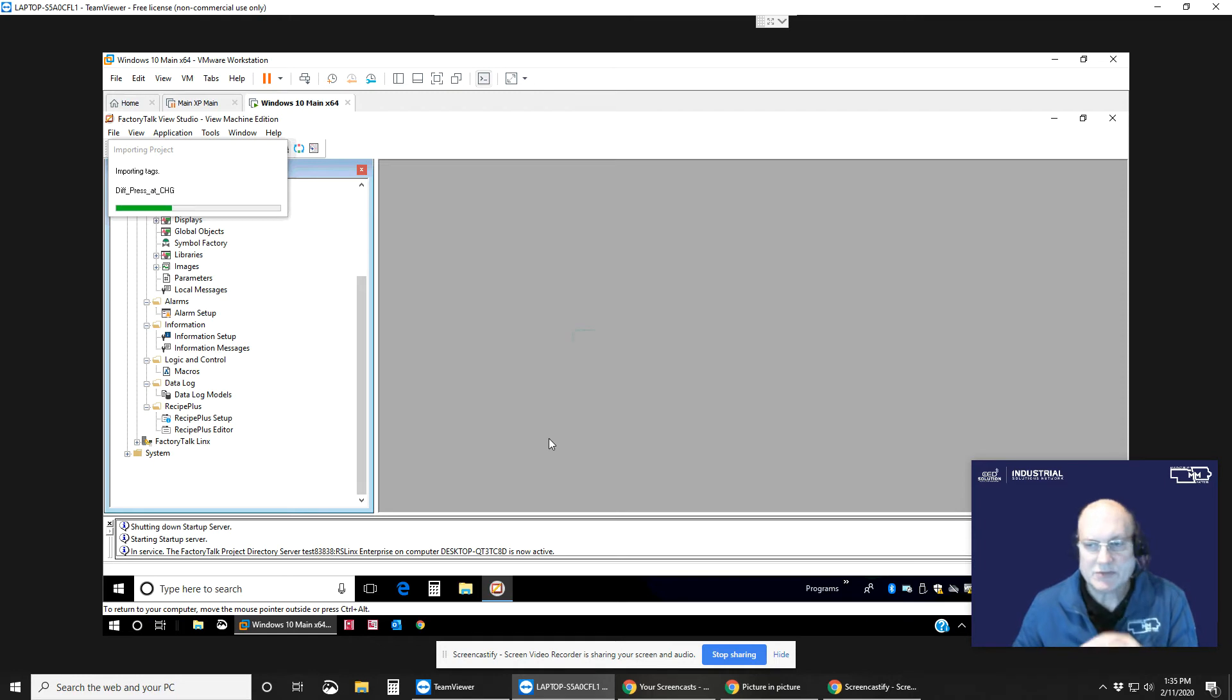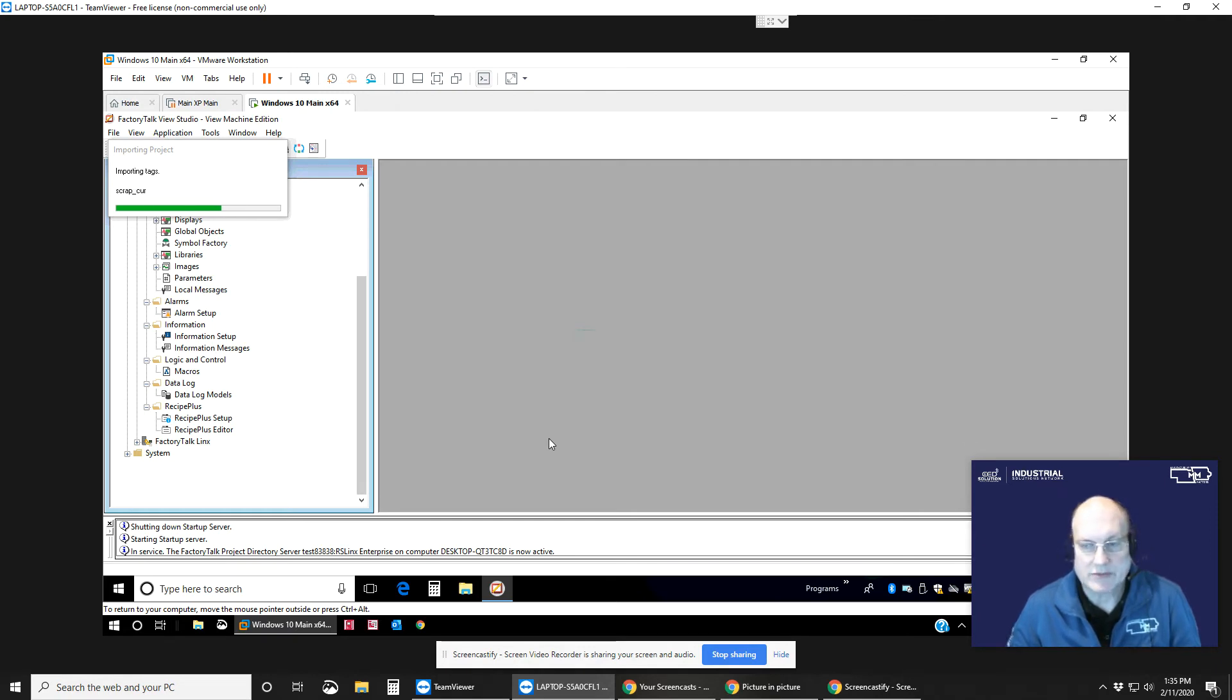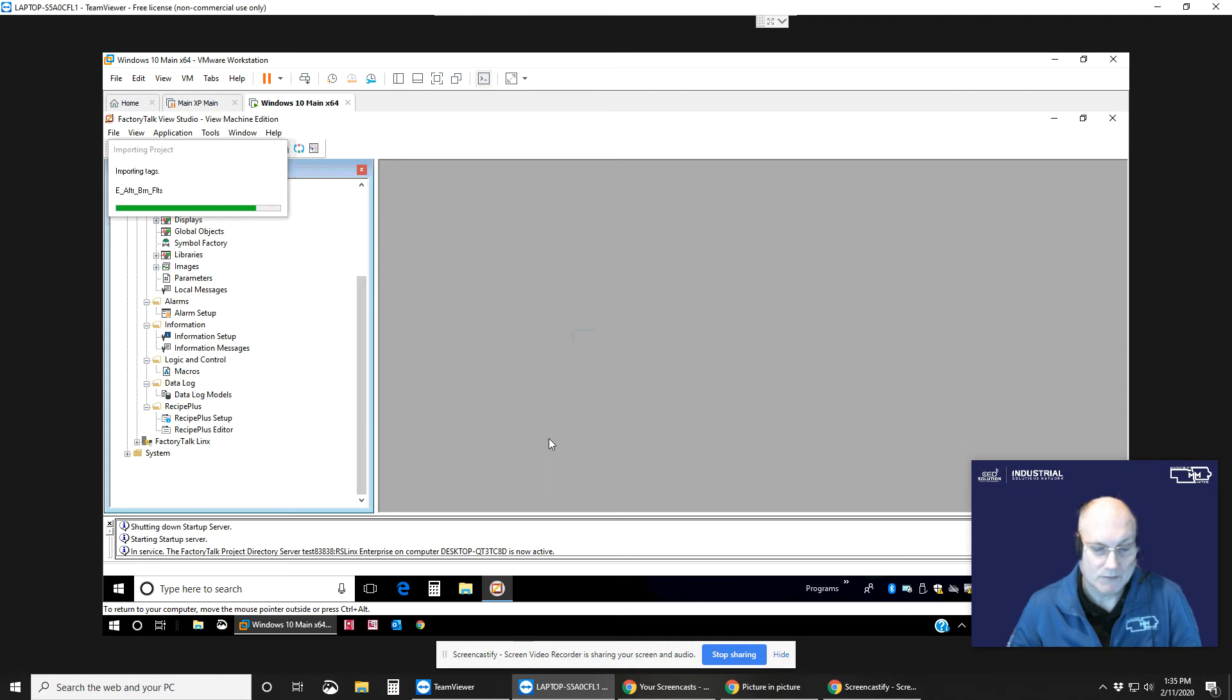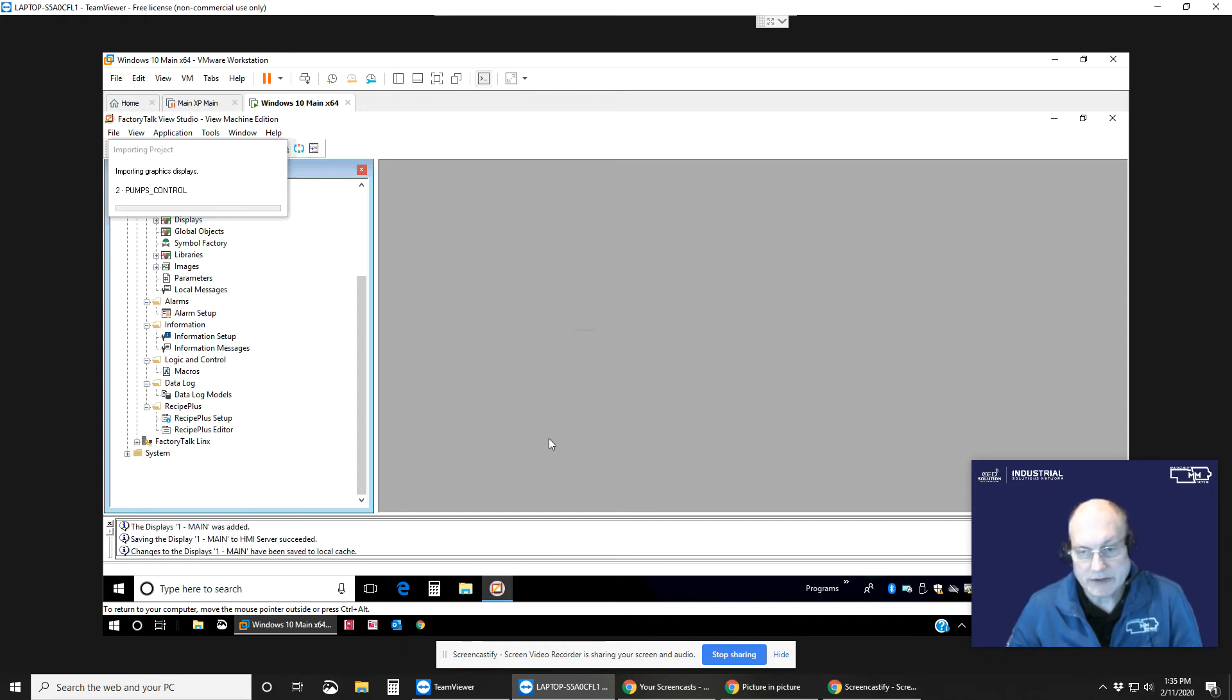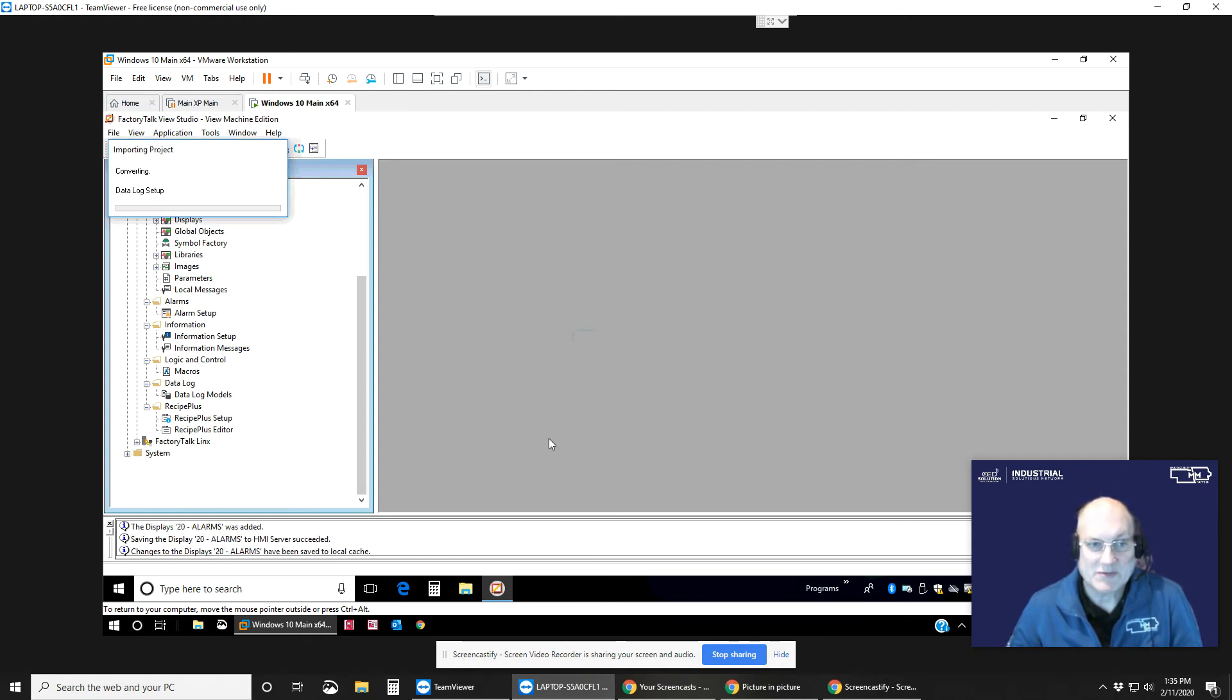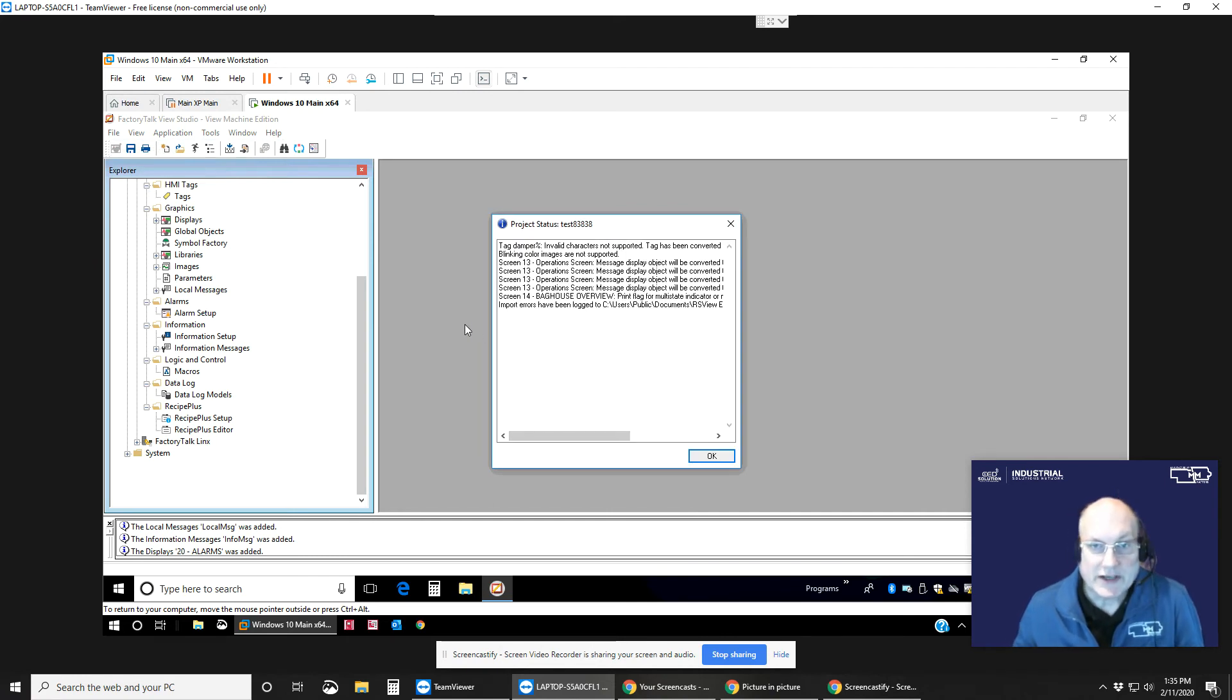The conversion process is pretty good. It will give a log file of what it didn't convert or certain screens, certain objects that may have been converted. You want to look at that later on. But for the most part, it does a very good job on its own. And this goes hand in hand oftentimes with the SLC or PLC5 conversion, where that converter, I would say it gets us 90-95% of the way there. This one does 99% kind of thing. Oftentimes the biggest thing is just relinking the communication path, honestly. Or that font issue there.